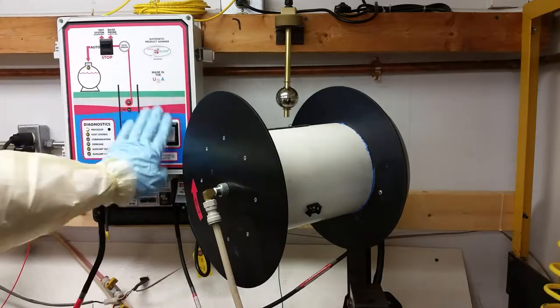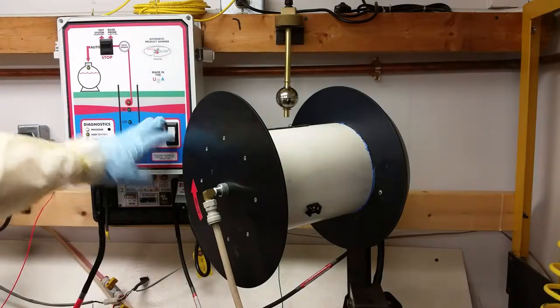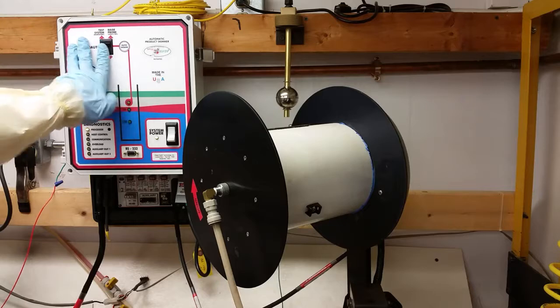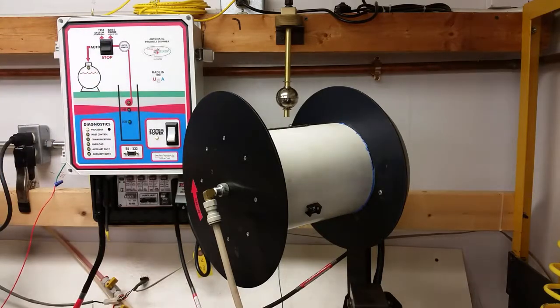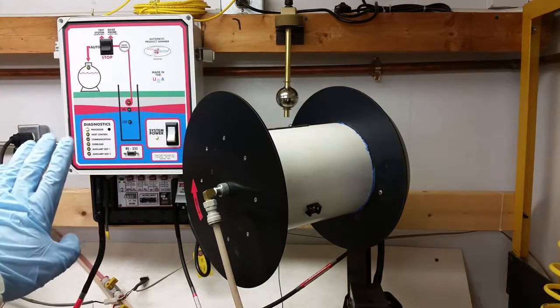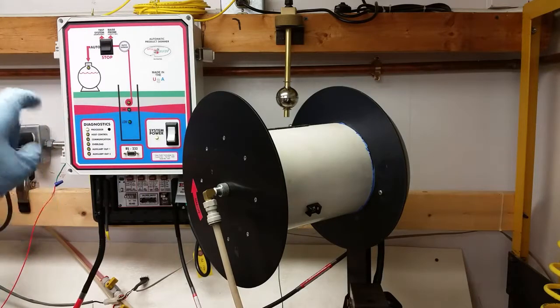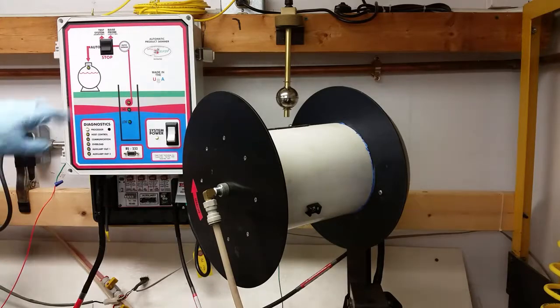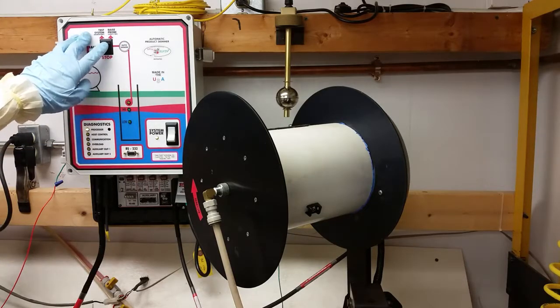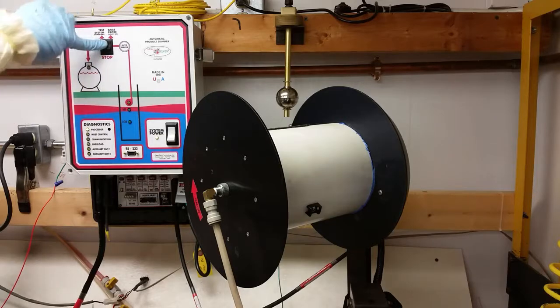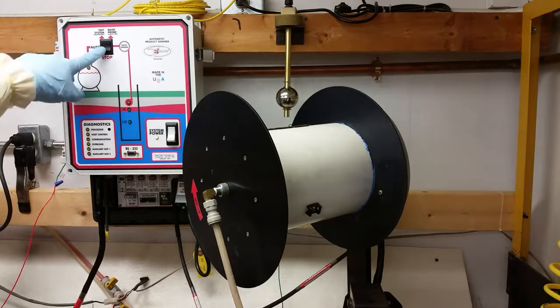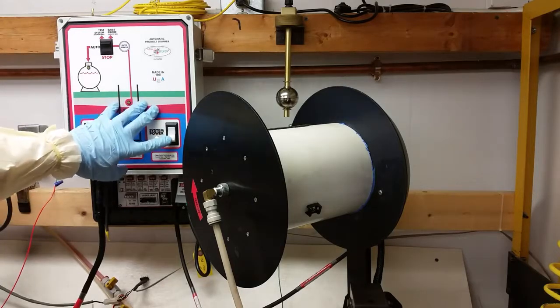System is on stop. We're going to power it down, and actually just to demonstrate that it's at its full downward limit, we'll set it to auto. There is a switch inside the box that just clicked. No reaction from the auto seeker. I'm going to stop it, and then we're going to try to raise the auto seeker, holding the PRC switch in the fully upward position. Nothing. Okay, so we're going to power the system down.